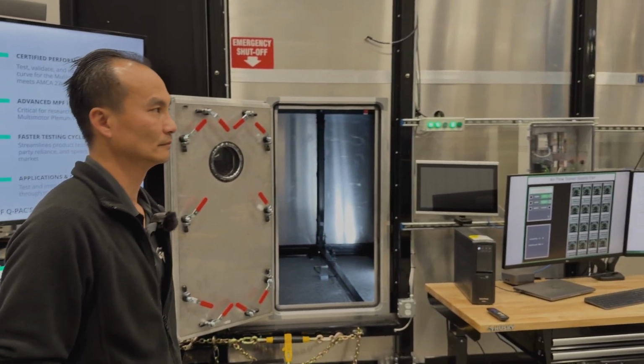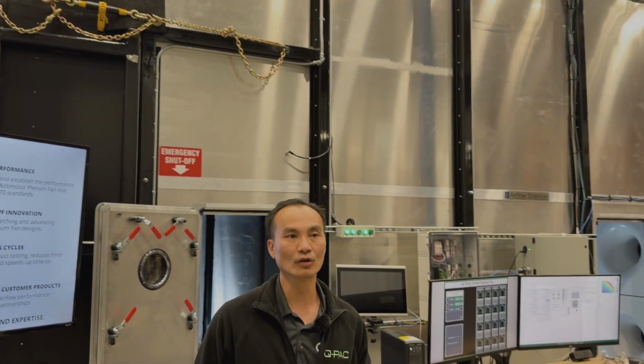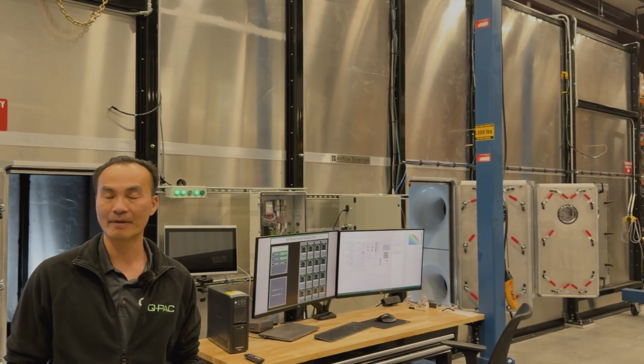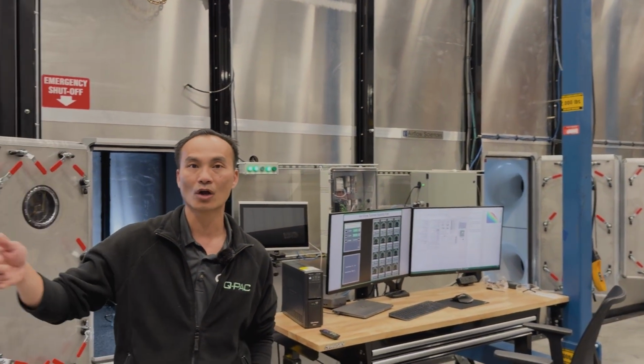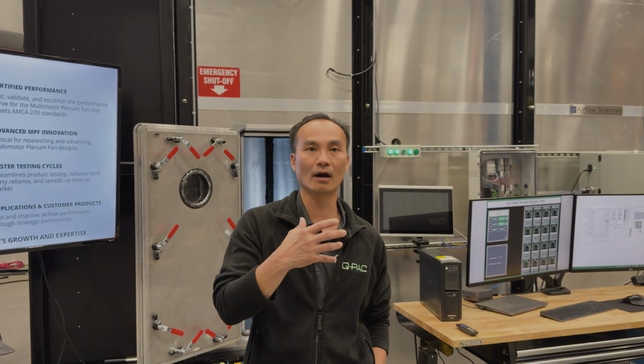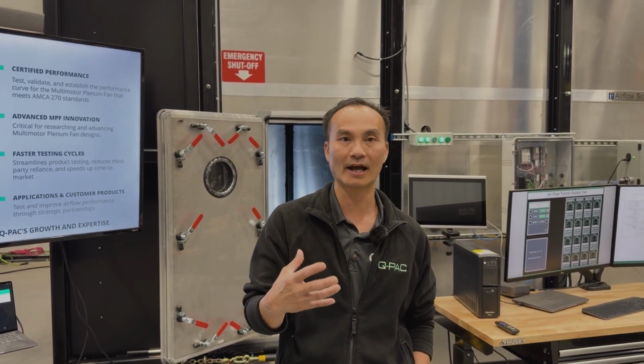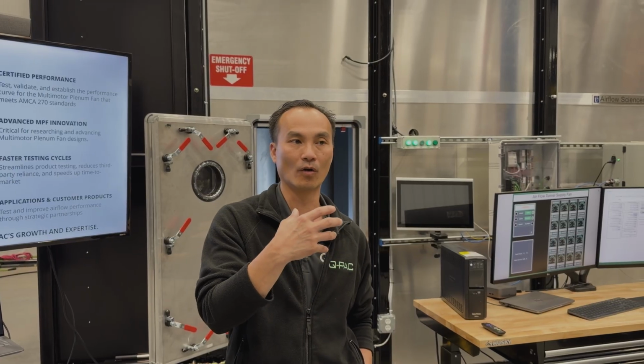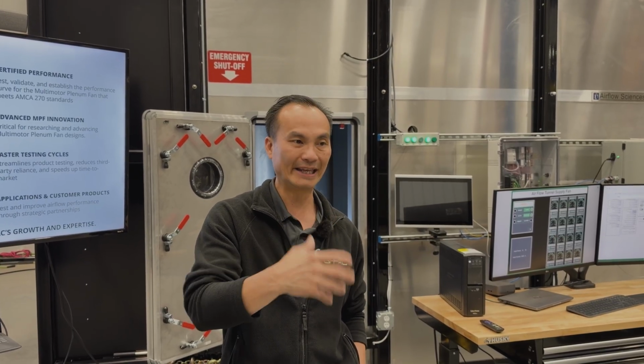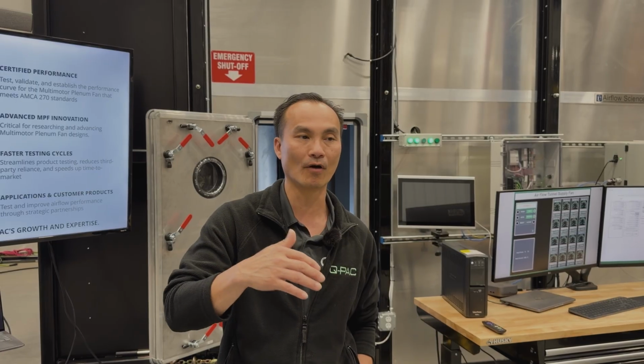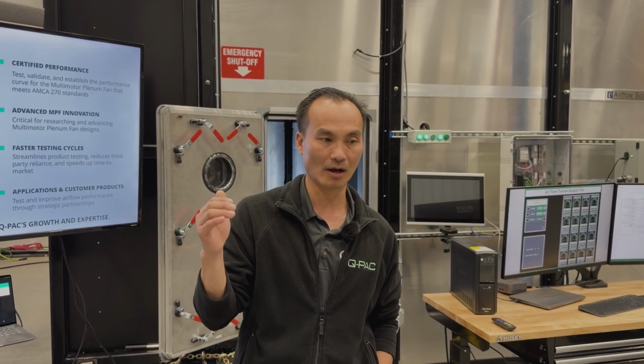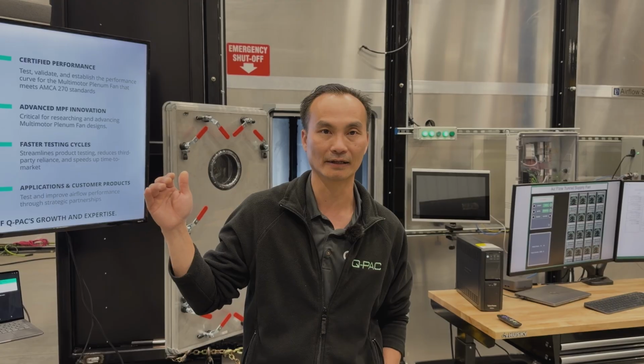But our biggest priority is testing to be AMCA certified. Ken, why is that important? Okay, so yeah, it's very important in terms of the accuracy because technically, if you look at any equipment manufactured today or in the past, when you have a single fan, an air moving device that is AMCA certified, that means they guarantee and almost meet the requirement of the performance, right? The public data is made by testing.